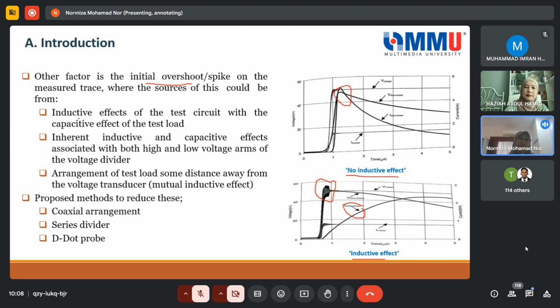So the inductive effect of the test circuit, when combined with the capacitive effect of the test load, because the test load, as I mentioned, should in general be represented by a capacitive component, like cable, switchgear, insulator, it should be capacitance. So when combined with the capacitance, it can give oscillation.